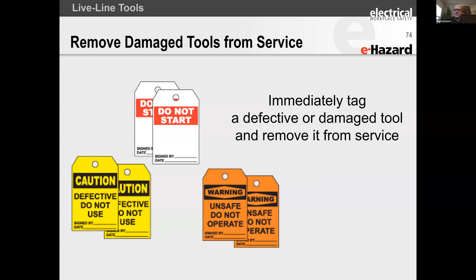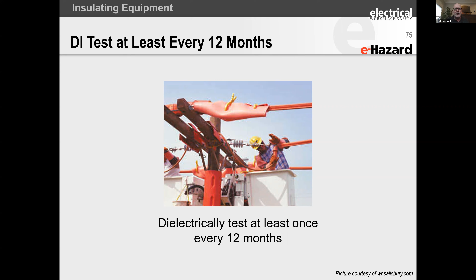And then all of your rubber goods, and we do glove in the US, and I know they started to do gloving techniques in the UK, just make sure that those are tested very regularly. We require by law that they be tested every 12 months and put on adequate cover-up. When I go out and investigate an accident when a worker has been hurt or killed doing gloving work, it's typically because they did not put on enough cover up or they did not seal it in place with these clamps so that something doesn't come uncovered if they bump it. And so that happens from time to time. It's fairly rare in the US now. We have really high quality training in that area for our electric utility workers, but just make sure that it stays in place and that it's tested regularly.